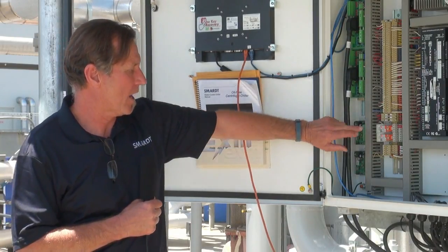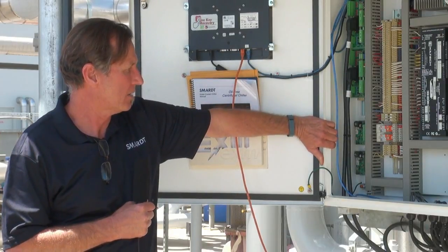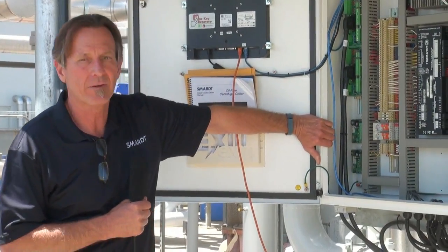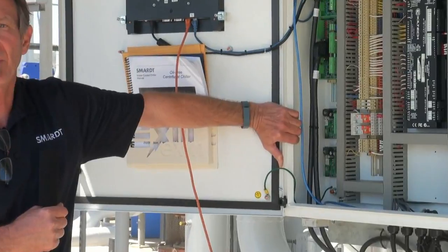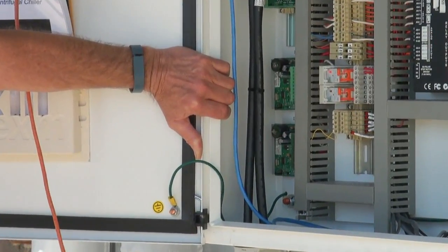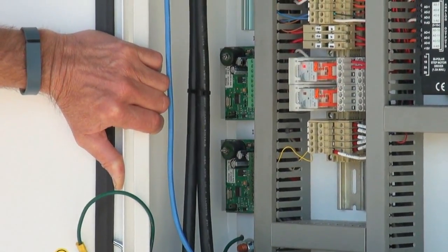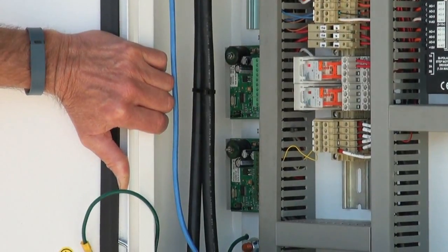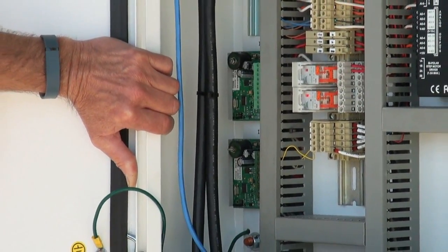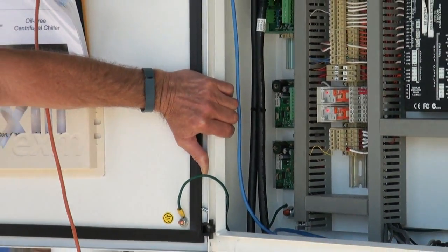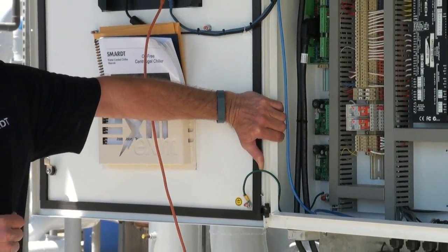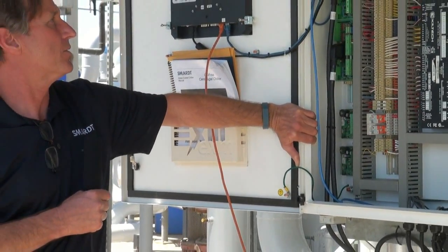You've got a couple of interlock relays. They do have LEDs on them, so they do light up when they're energized. They do need to energize before the chiller will run. So that's something to eyeball, something to look at if you're wondering why your chiller's not running.